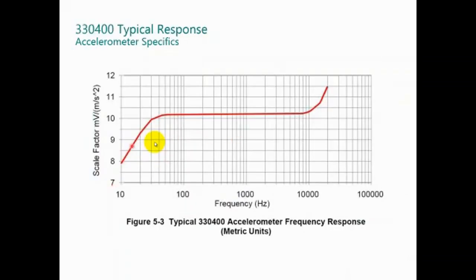Here is the typical response from an accelerometer. To review the information, go to the manual. 330400 is the accelerometer part number. You can see, starting at 10 Hz and the maximum is around 20 kHz. All the tests are made at 100 Hz per specification. This is specified in the transducer data sheet.